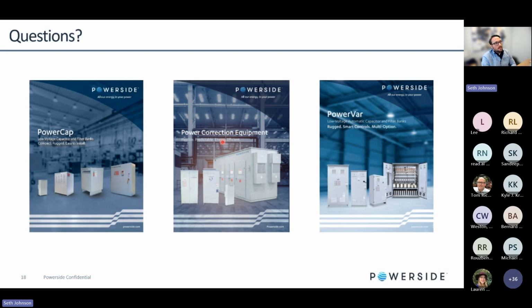based on where the source of power is coming from. And this can go for also a cogeneration site, or if you totally go into an island mode, where we need to make some adjustments for how we do the compensation. And that's very easy to do with active harmonic filters, because they also provide reactive power compensation, phase balancing, and harmonic mitigation. Great point.